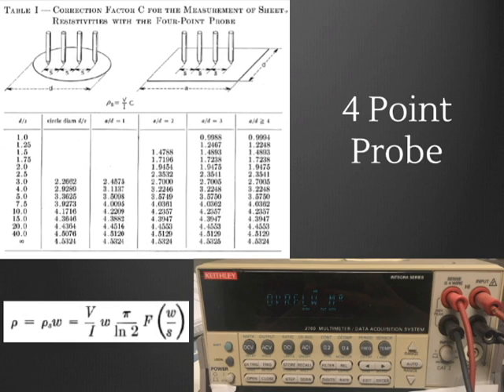These measured values from the four-point probe give the sheet resistance by calculating the voltage to current ratio. A correction factor C is then applied to account for the geometry of the sample. The table here shows various values for C depending upon whether a circular or rectangular sample is probed. The circular samples are dependent only upon the diameter to probe spacing ratio. The rectangular samples are similarly calculated with an additional length to width ratio. The bottom left equation shows how the resistivity and thickness can be calculated from the results of the sheet resistance measurement.